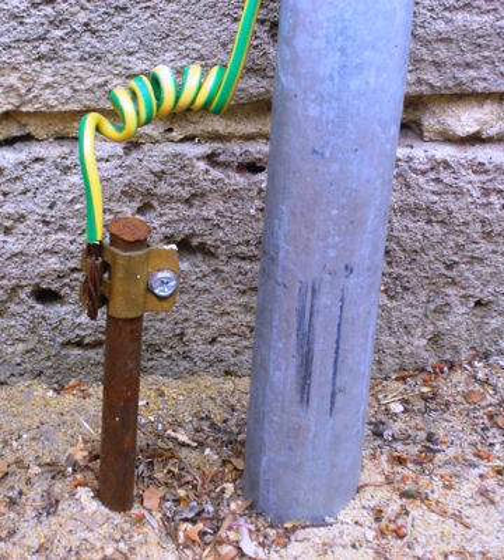For particularly demanding applications, the main technical ground may consist of a heavy copper pipe, if necessary fitted by drilling through several concrete floors, such that all technical grounds may be connected by the shortest possible path to a grounding rod in the basement.